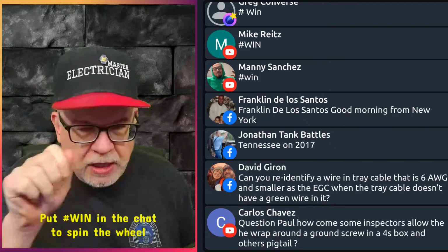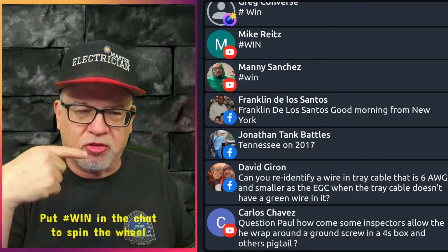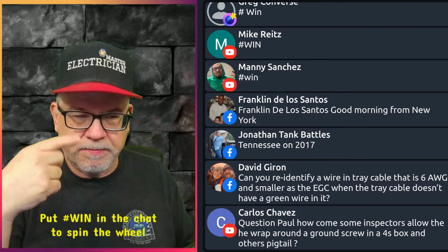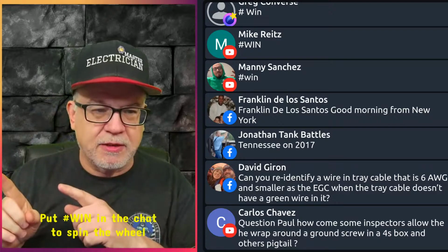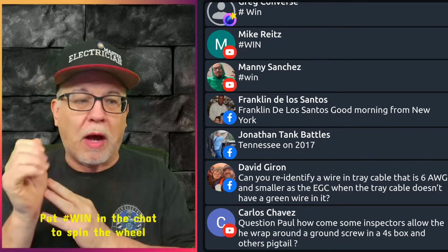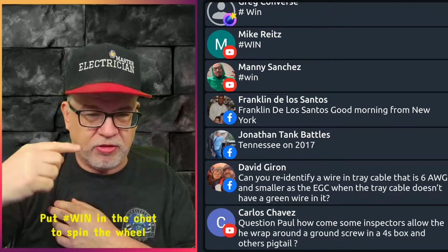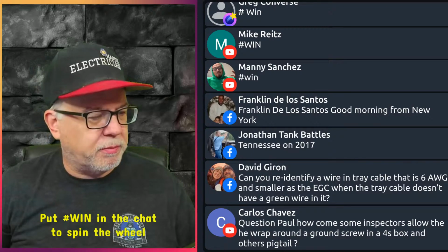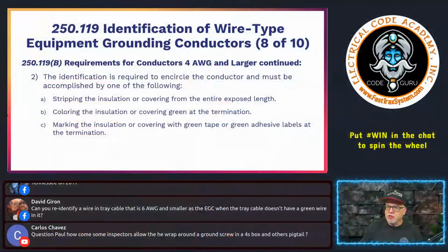Now, a lot of people will take it and use a little Sharpie. Even in that requirement in 200.7 as well, you're required to encircle it. Okay? So just marking it on one side doesn't qualify. Same here. Just putting something on one side is not going to qualify. It has to encircle it. So wrap it around with tape, something of that nature, then that's going to meet the requirement. So again, it encircles the conductor and must be accomplished by one of the following.